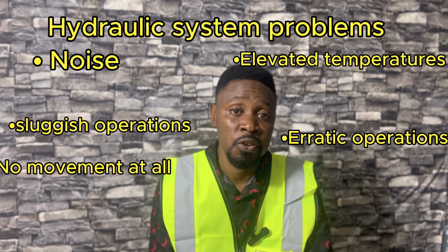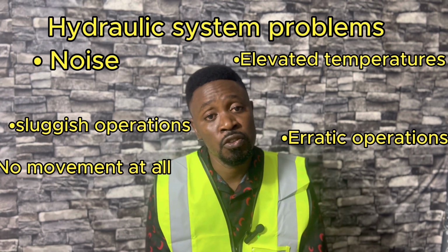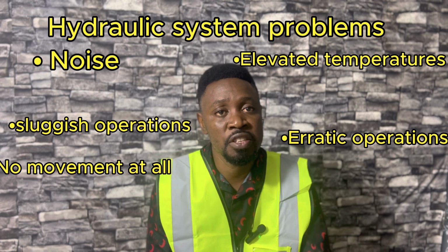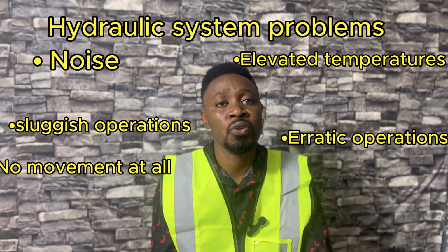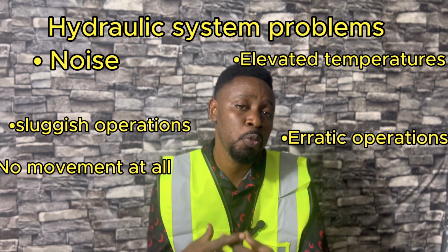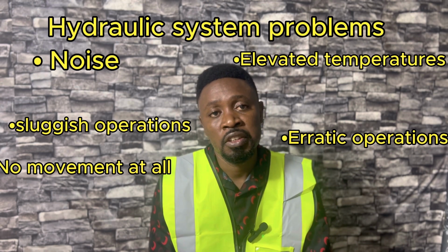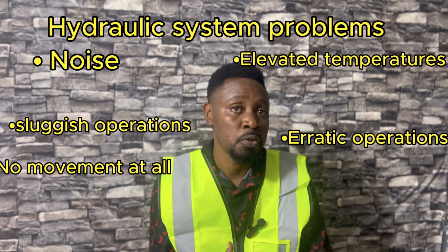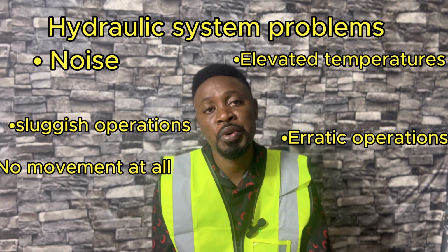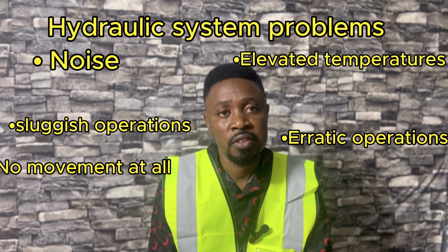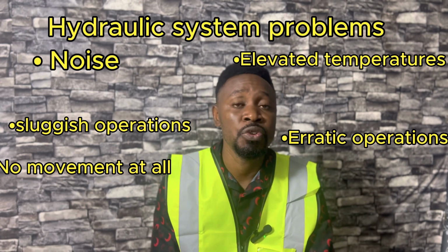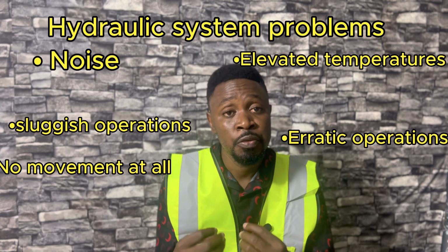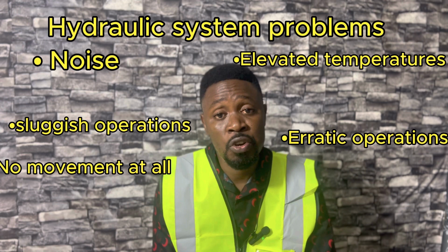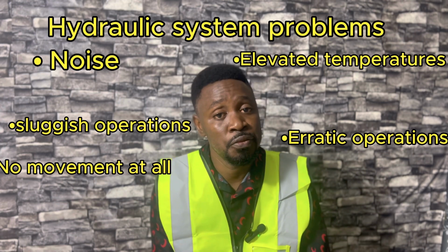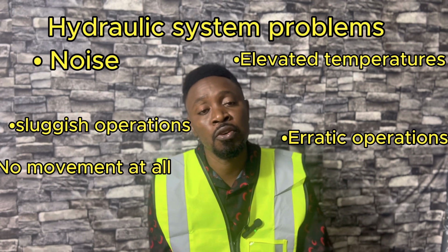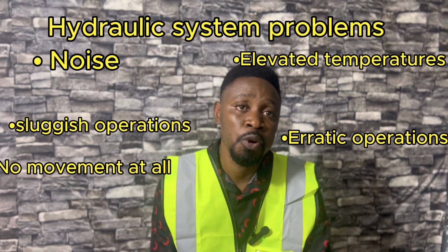Now, we've already discussed aeration and cavitation. Aeration is due to the fact that air leaks into the system and mixes with the hydraulic oil, thereby causing the hydraulic oil to operate spongily. Now, this oil becomes compressible due to the properties of air, so it is sluggish in operation. It causes pitting on component parts of the pump, such as the pistons, vanes, gears, depending on which type of hydraulic pump is being used.